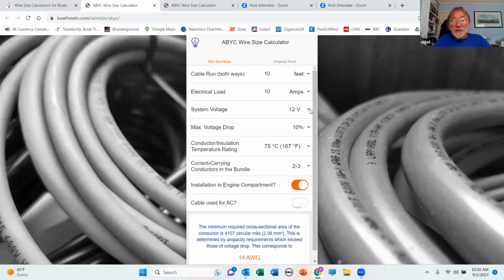Let's go ahead and change this to 3% and see what happens. We're still at 14 gauge because we've changed the voltage drop requirement from 10% to 3%. But once again, ampacity is still driving this because it's such a short conductor run. And so the ampacity issue remains the same, and we need a 14 gauge conductor. And let me put this back to 60 feet, and we'll see what happens.